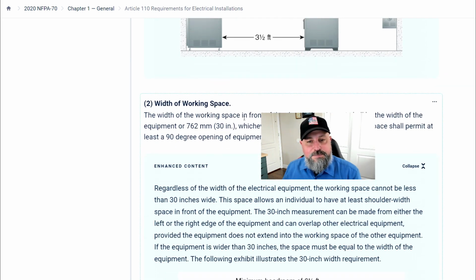Width of working space. The width of the working space in front of the electrical equipment shall be the width of the equipment, or 762 millimeters (30 inches), whichever is greater. In all cases, the workspace shall permit at least 90-degree opening of equipment doors or hinges. So around equipment, it needs to be at the very least 30 inches of space for that equipment. So they can't be right next to each other.